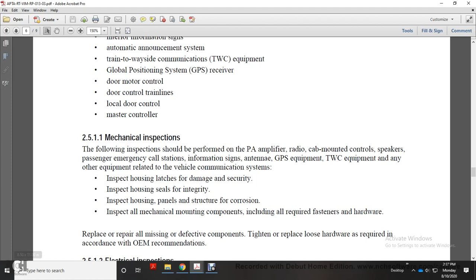2.5.1.2 Electrical inspection. The following inspection should be performed on the equipment in the previous section. Check wire insulation for cuts; repair or replace if required. Check wire for loose, crimped, worn, bent, or eroded lugs; replace or repair if required. Check wire for loose terminals; tighten if required. Check wire for heat fatigue; replace or repair if required. Check connectors for damage and ensure there are no misaligned contacts; repair or replace if required. Check relay contacts for burning, pitting, and deformities; clean, repair, or replace if required. Check fuses for burns, separated elements, or other damage; replace if required. Note: the reason for the blown fuse should be found and corrected.